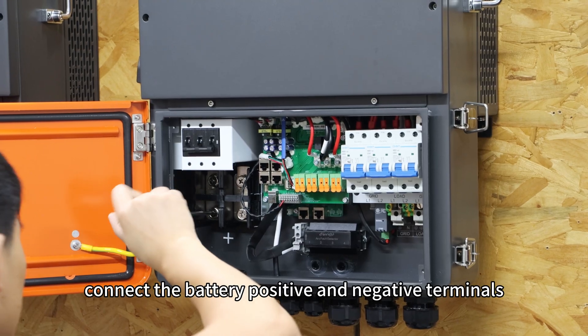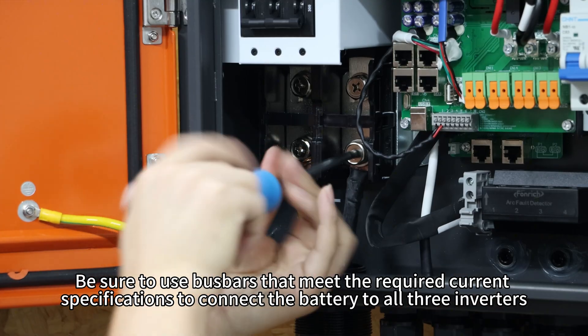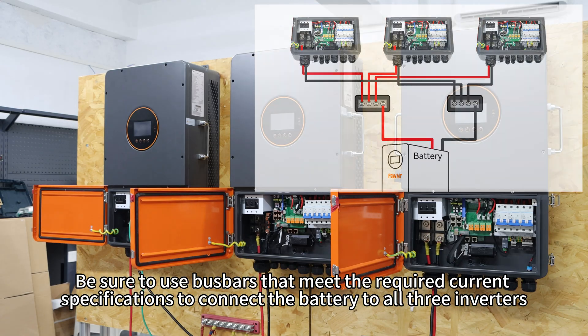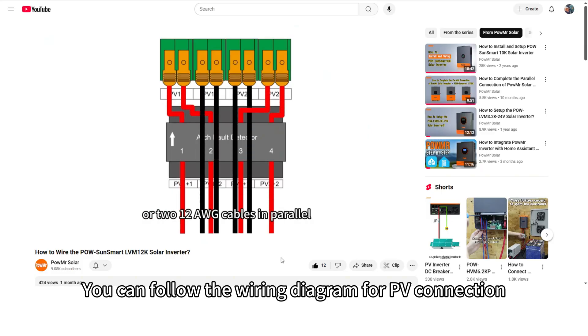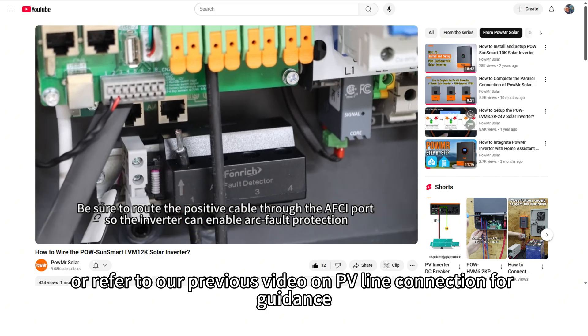Now connect the battery positive and negative terminals. Be sure to use bus bars that meet the required current specifications to connect the battery to all three inverters. You can follow the wiring diagram for PV connection or refer to our previous video on PV-Line connection for guidance.